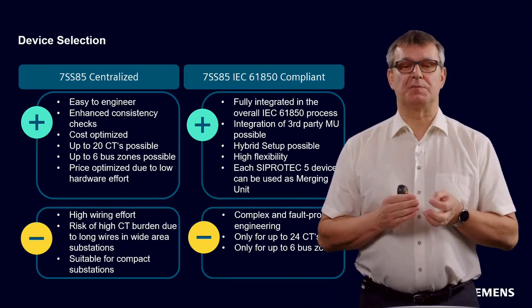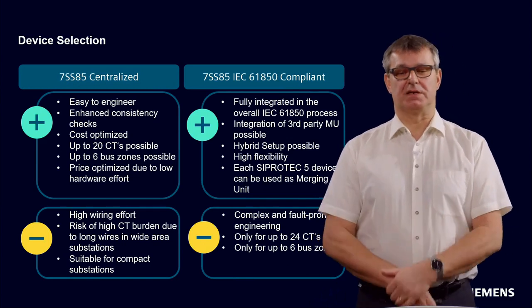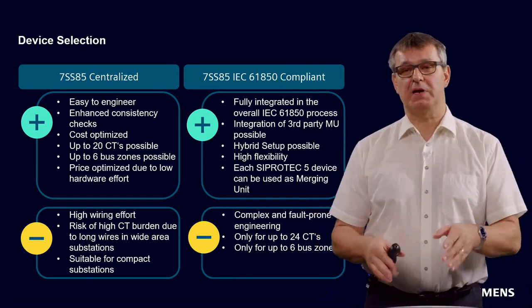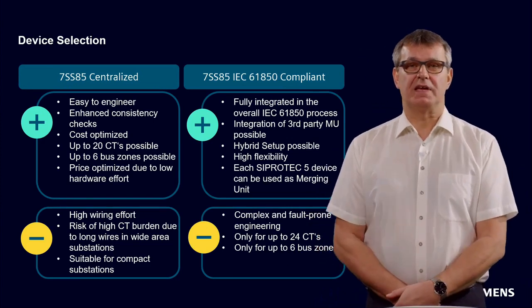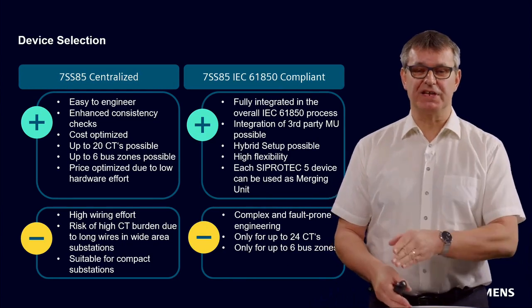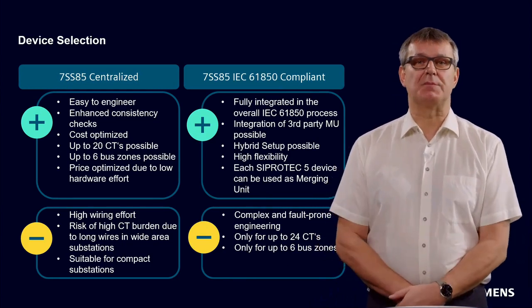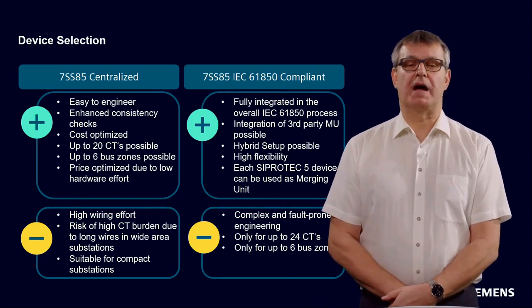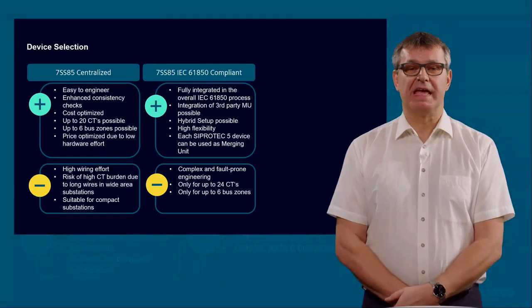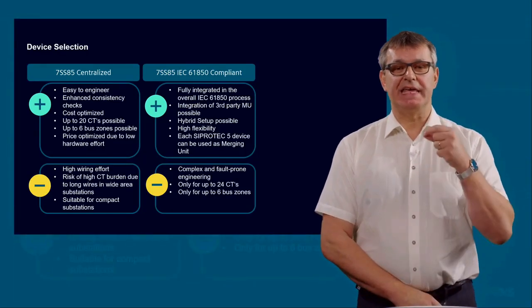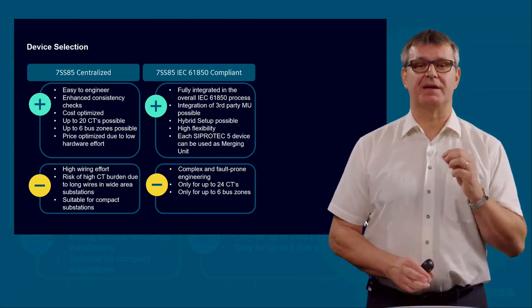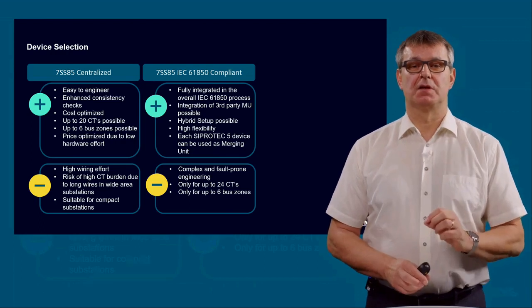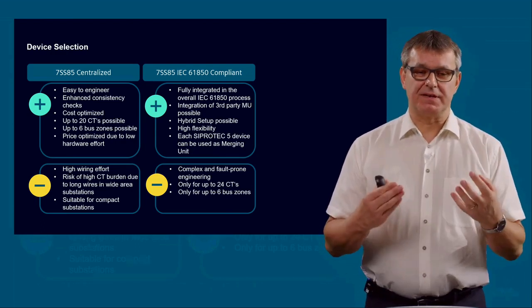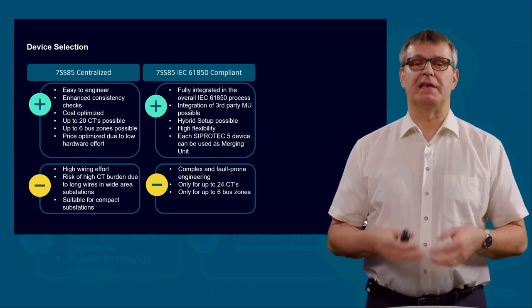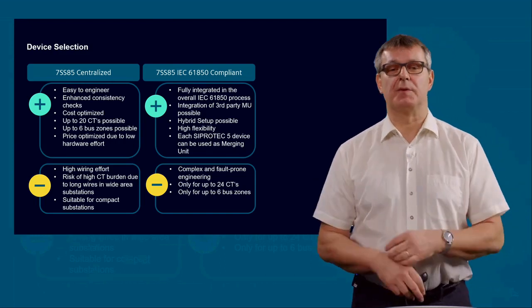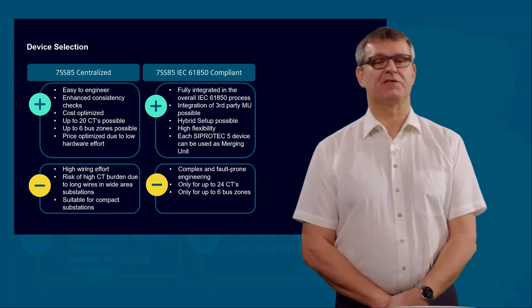Typically, we are using a distributed busbar protection, locate the 7SS85 device in a coupler, and we make a centralized wiring to the coupler, to the 7SS85, whereas all the feeders will be assigned by the distributed approach. And this is a common general advantage in our 7SS85 SIPROTEC 5 distributed busbar protection. Each SIPROTEC 5 device can be used as a merging unit for the distributed busbar protection. For example, also a 7SL86, 7SL87, a line differential protection, but also distance protection, transformer protection, each device which is in the SIPROTEC 5 portfolio.